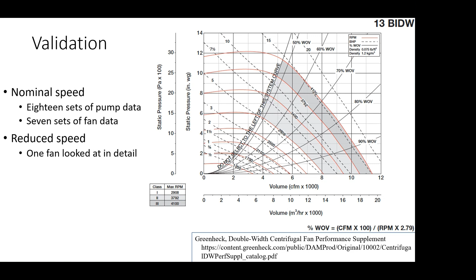For one fan in particular, we have results showing efficiency versus flow rate and pressure, then power versus flow rate and pressure. Each figure has two lines: one representing interpolated data from the power maps, and one representing model output using the Euler number method. In the first two figures we mainly see just one line, which is good news—it means the efficiency computation was successful in capturing the actual values from the power maps.